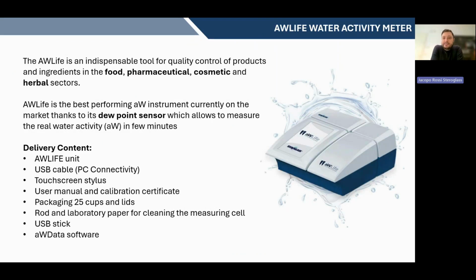But let me introduce you a little bit to our solution, the aWLife. That is an analyzer developed for the food, pharmaceutical, cosmetic, and herbal sectors. Our instrument is based on the dew point sensor, the first one we have seen before. That is the sensor that is in conformity, for example, with the ISO, the AOAC and the pharmacopoeia. So it's a sensor that grants you the accuracy and the repeatability that are required for this kind of international regulation. You may consider that the instrument, when it comes to you, is already ready to work.